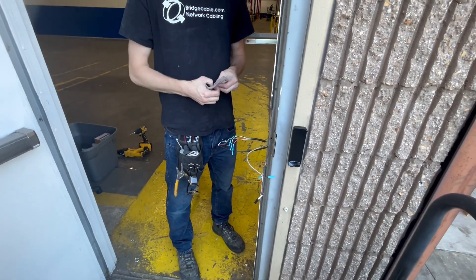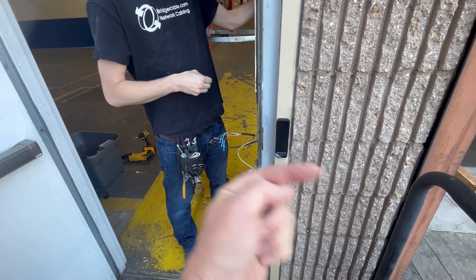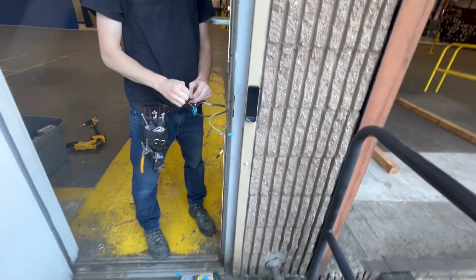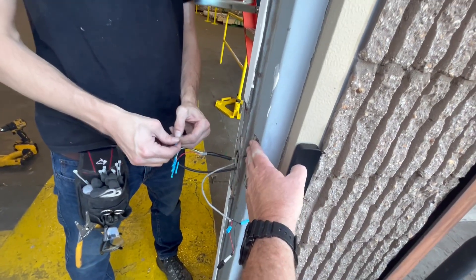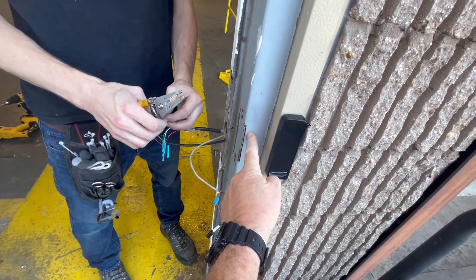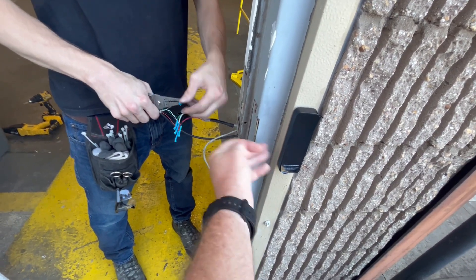The reason why we're using four wires is it's RS-485 — the signals are bi-directional, they go back and forth. Verkada has that. So installing this reader, just swapping it out. This one is pre-existing, but they worked the door frame, they got the 22/6 wire, and in this particular situation it's a nice hollow frame — they were able to put all the connections right inside of here.